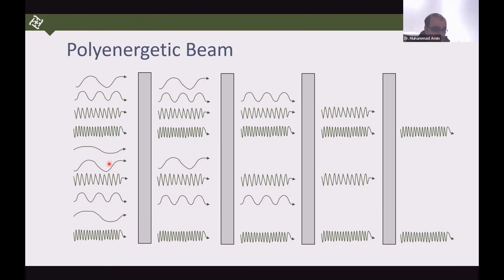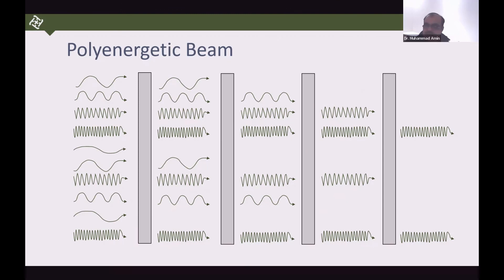Because of average energy and penetration power, high energy photons can penetrate more. When filtration is added, low energy photons are filtered out, leaving high energy photons. This improves the quality of the beam, but the quantity or intensity of the beam decreases.